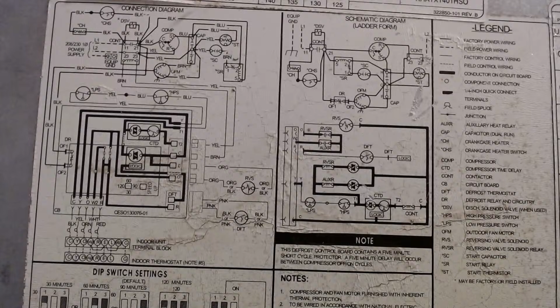Let's start with our Y circuit. Go over Y through our logic board out - the first thing we're going to hit is our low pressure switch, so everyone can see LPS. If you're not sure what it is, you can go to your legend and it says low pressure switch - legends are great to give you the definitions of the terminals. Go through our low pressure switch so you can see how your switch is drawn; it opens on a fall of pressure.